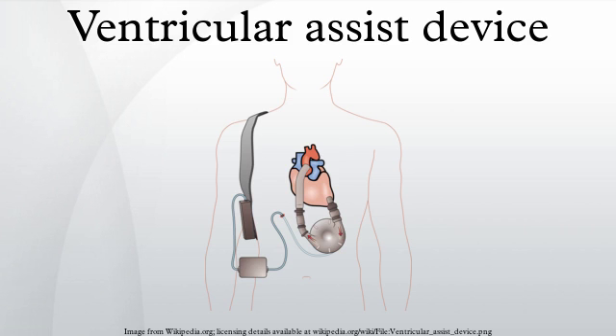The pumps used in VADs can be divided into two main categories: pulsatile pumps, that mimic the natural pulsing action of the heart, and continuous flow pumps. Pulsatile VADs use positive displacement pumps. In some of these pumps, the volume occupied by blood varies during the pumping cycle, and if the pump is contained inside the body, then a vent tube to the outside air is required. Continuous flow VADs are smaller and have proven to be more durable than pulsatile VADs. They normally use either a centrifugal pump or an axial flow pump.